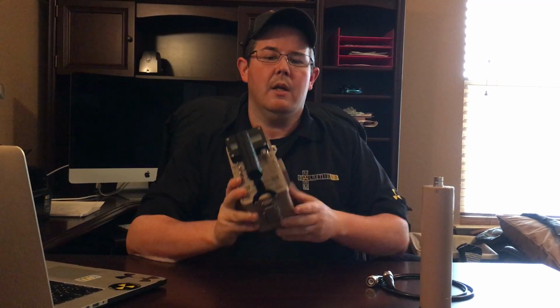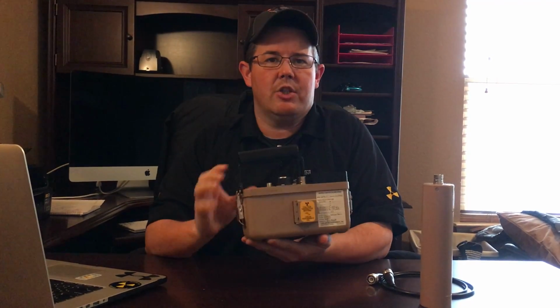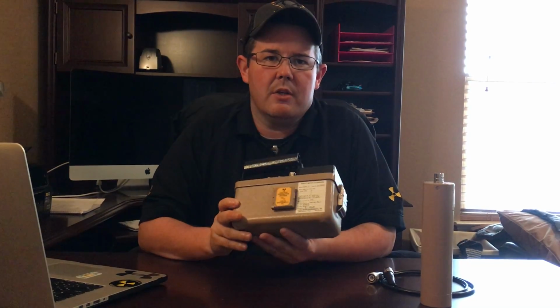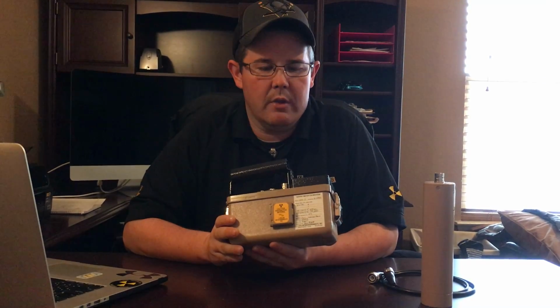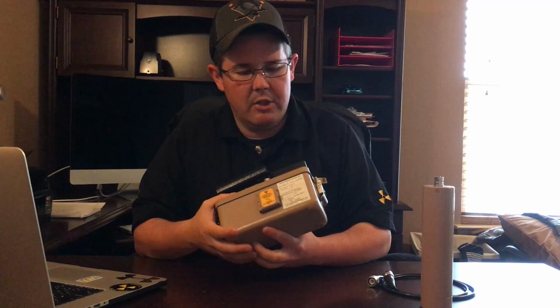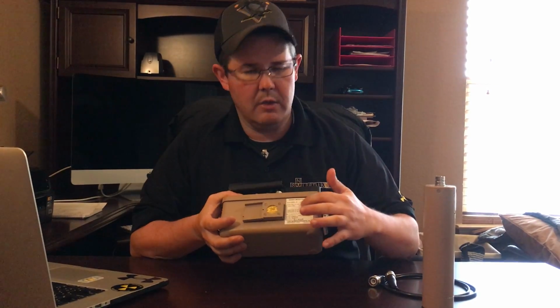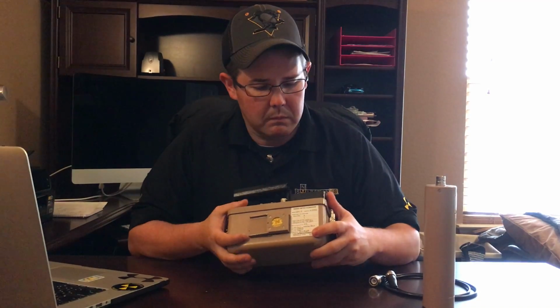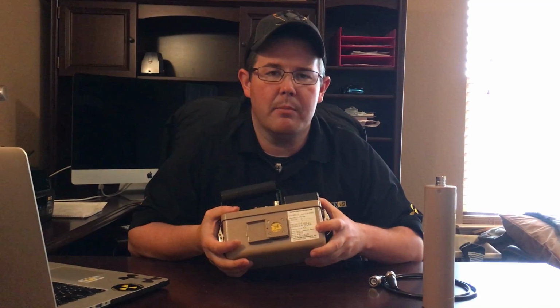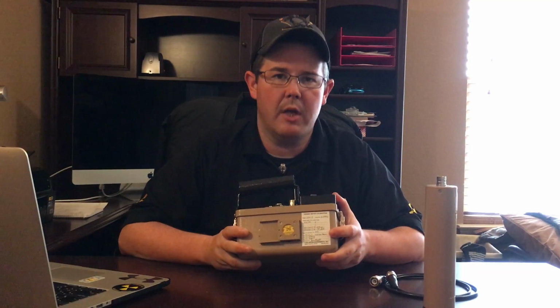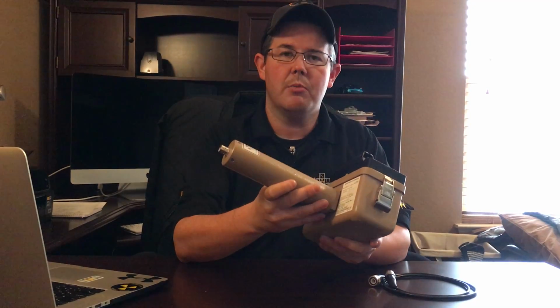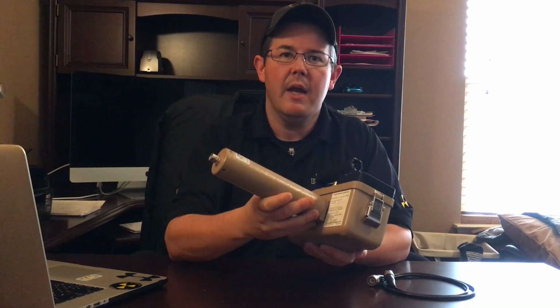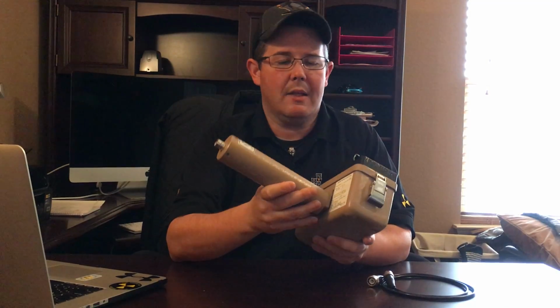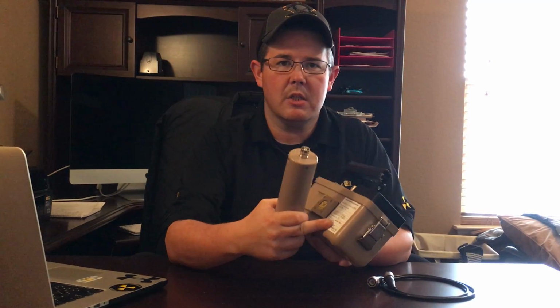Moving on, this meter does have a check source, so we would have to do a response check to make sure that this meter is working properly. Right next to the check source, there is a calibration sticker. This calibration sticker is used to do your response check. To do that, I would have my probe hooked up, and I would place my probe completely up against the meter itself, and it would give me a reading. I would check that reading against the calibration sticker to make sure that this meter is working properly.